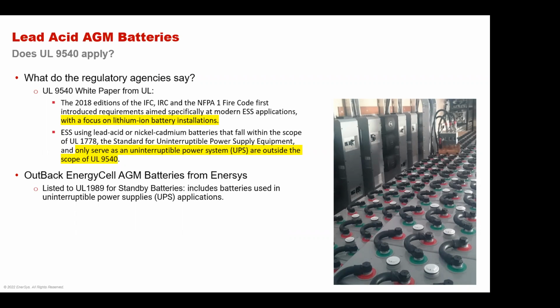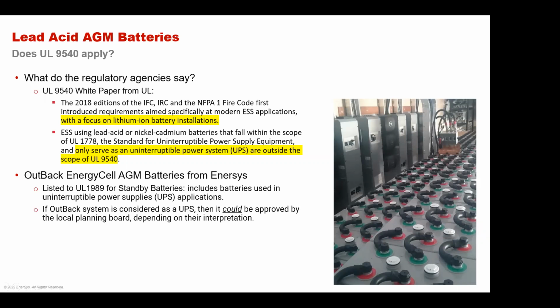But now UL 9540 does apply, and it does include AGM batteries, but these comments up here highlighted in yellow do tend to make one think that maybe there's some gray area here, because we've always told people, well, it's a UPS battery, then maybe it could be approved by the local planning board depending on their interpretation of this. Is it an exception? Is it outside the scope of UL 9540? Technically, no, because it's UL 1989 and 1778. But it kind of depends on what code cycle they're on. Have they adopted a code cycle that compels them to only approve UL 9540 energy storage systems? And we think it's a good idea.